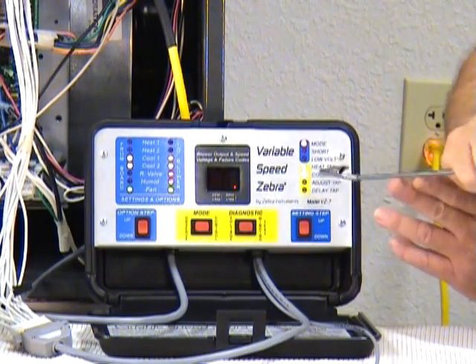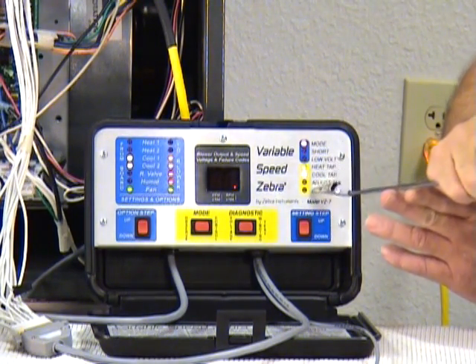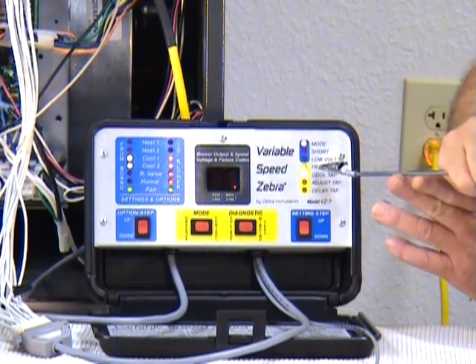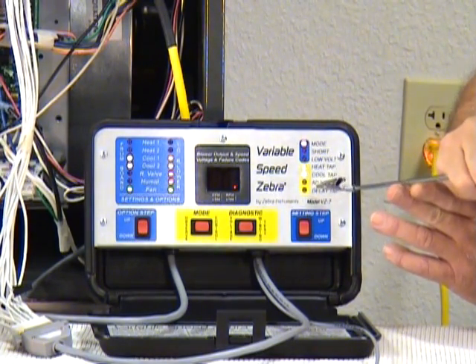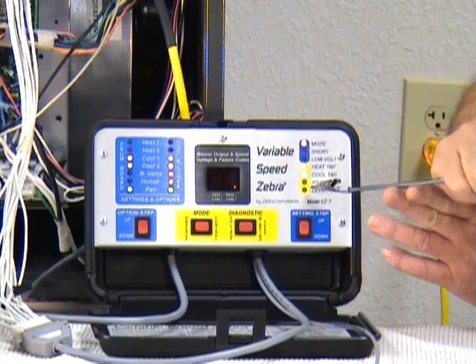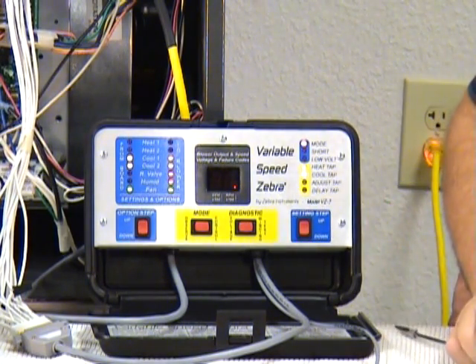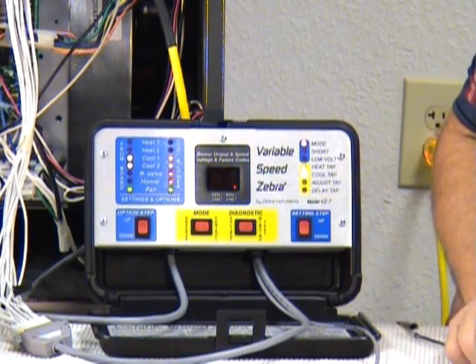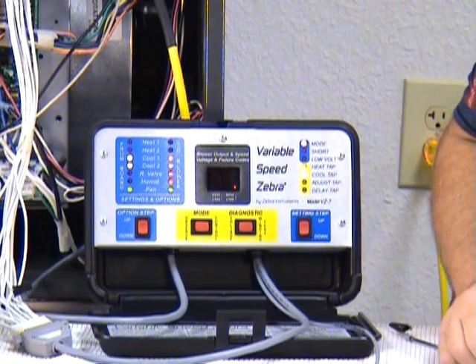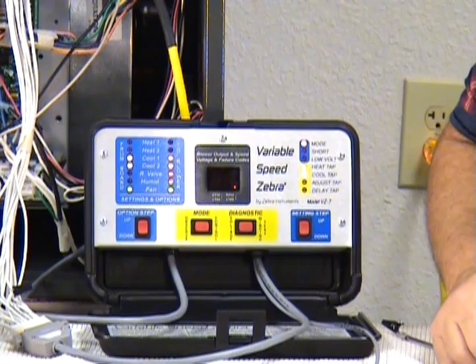There are also 4 signal lines that control the taps that cannot be varied every day, i.e. you're setting those with a dip switch or with a jumper. Those 11 lines give your motor quite a bit of versatility in providing your customer with good conditioning.